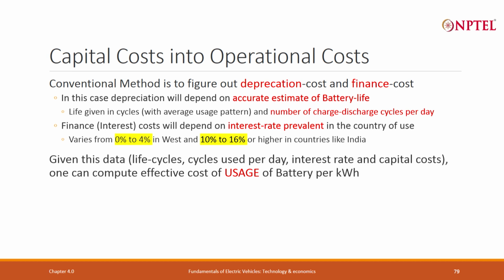Given this data, life cycles, cycles used per day, and of course life cycles itself depend on temperature, the depth of discharge used, and the rate of charging and discharging. Let us assume you fixed all this and got the life cycles. Then you need cycles per day, interest rate, and capital cost. So there are four things: life cycles, cycles per day, interest rate, and capital cost. Then one can compute the effective cost of usage of battery per kilowatt hour.